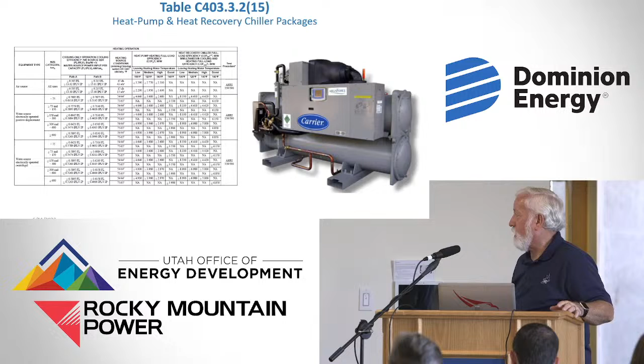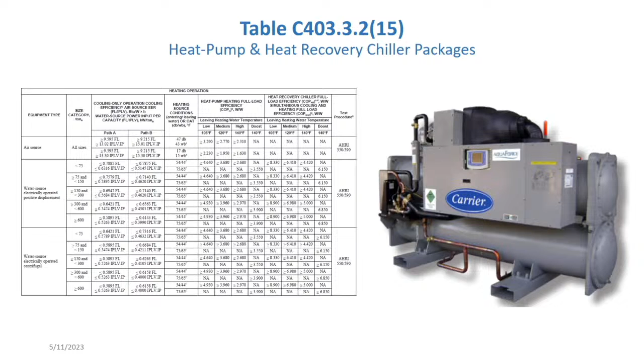A chiller, as I mentioned earlier, I think, chills water and sends it out through a building. You can move more BTUs in water than you can in air. And so when you get a big building, circulate hot water, circulate chilled water, and you can move BTUs in and out of the building a lot more effectively when you have long runs. You also can have some heat recovery built into your chillers. It's a little more complex. We won't go into it. If you want to talk about it, we can after, or you can send me an email. But they have some efficiency requirements there too.